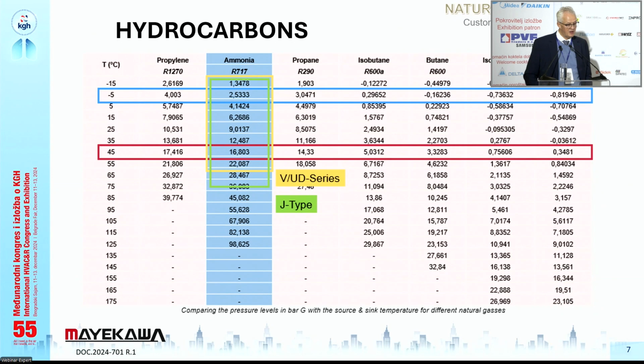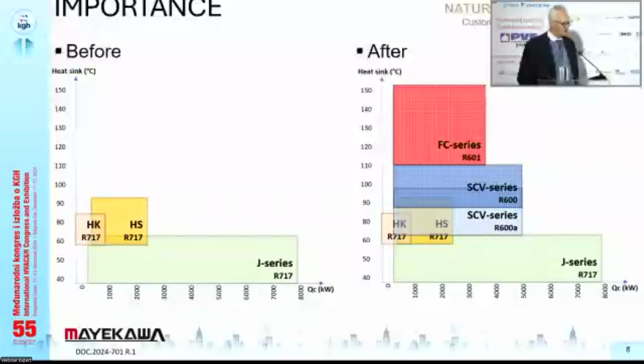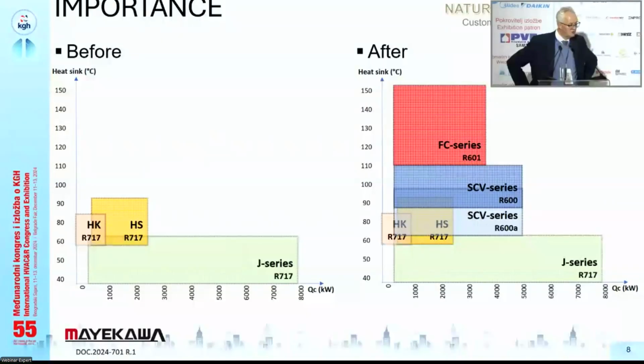The J-type is a 30 bar compressor. You can see that in the ammonia column. It is the green square, and you will see that even with pentane, I go to the most extreme hydrocarbon you see here with the lowest pressures, and you see there that we are even not yet at 1 bar.